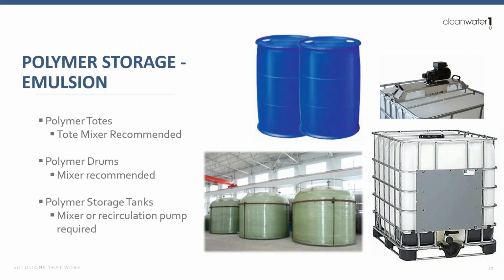So polymer storage, this is something that every plant has to deal with. How is the polymer being delivered to site and where is it being stored? When we're referring to emulsion polymer, generally there are three ways to do this. We can use polymer totes, polymer drums, and polymer storage tanks. What type of storage we use depends on the rate at which we're using that polymer. For smaller applications, we may be using a polymer drum. Medium to large applications, we're using totes.